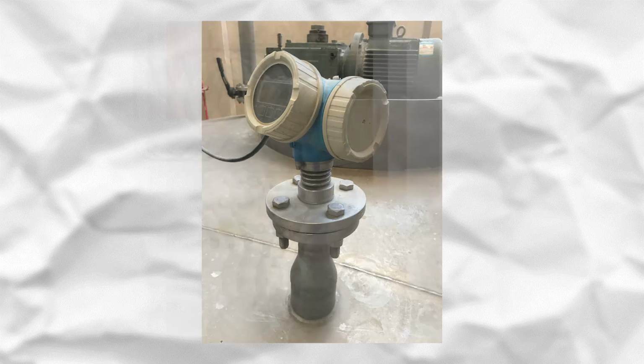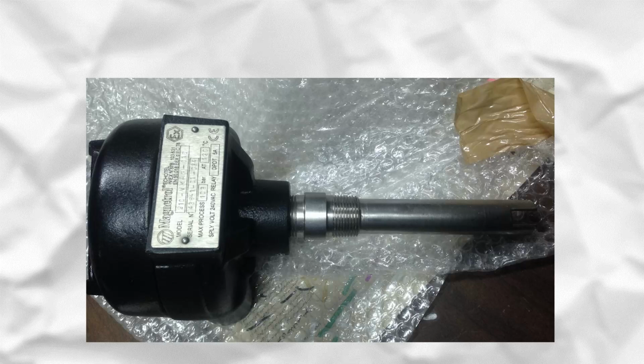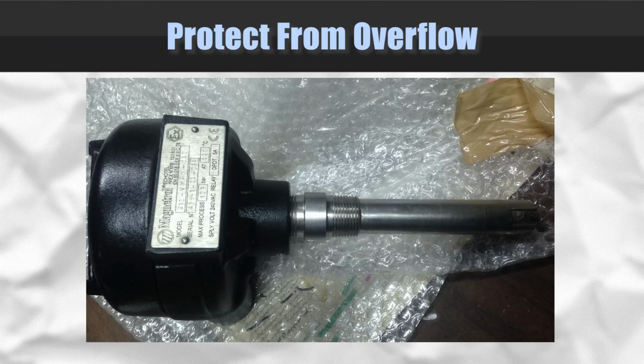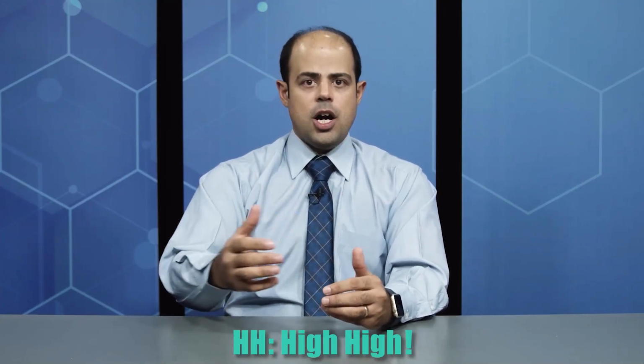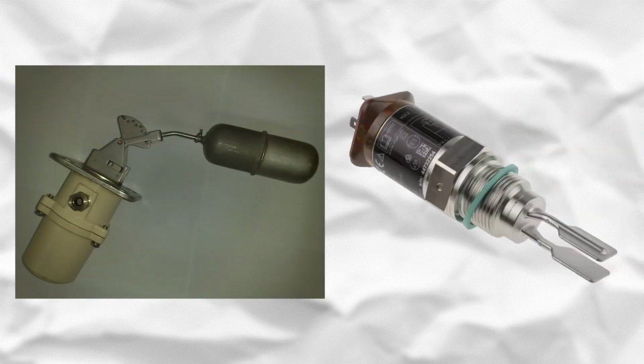by these level meters. Level switches are widely used in different industries to protect a vessel or a drum from overflow. You can design a drum and consider a set point for the highest level called high high. A floater level switch or a tuning fork type could be installed on the elevation, and in case of fluid reaching, the related contact is changed. If the electrical contact used to be a normally closed one, it changes to open. Consequently, this digital signal is sent to the control room and the operator supervising the system is informed of the high status at the site.